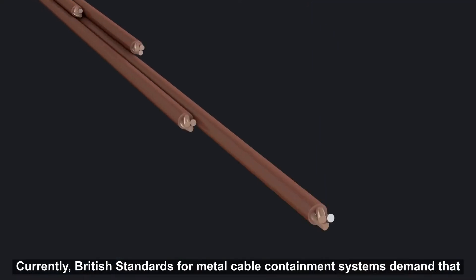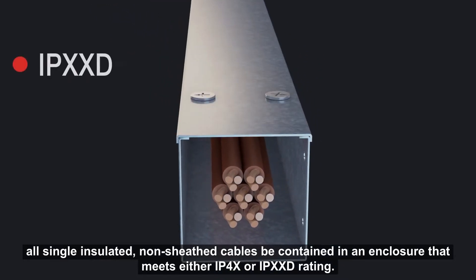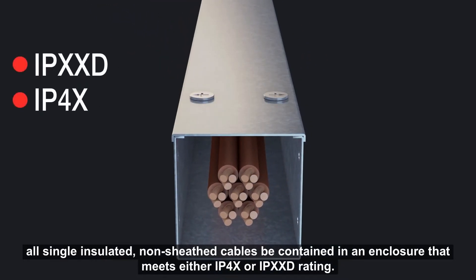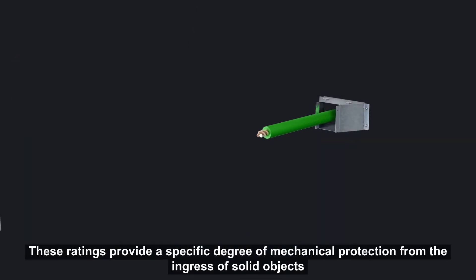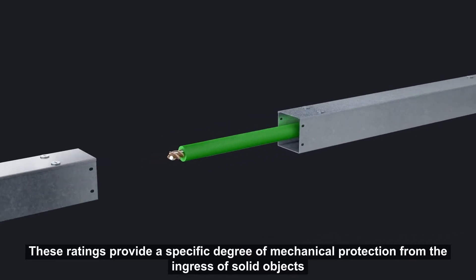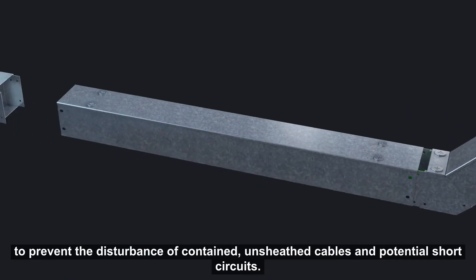Currently, British standards for metal cable containment systems demand that all single insulated non-sheathed cables be contained in an enclosure that meets either IP4X or IPXXD rating. These ratings provide a specific degree of mechanical protection from the ingress of solid objects to prevent the disturbance of contained unsheathed cables and potential short circuits.